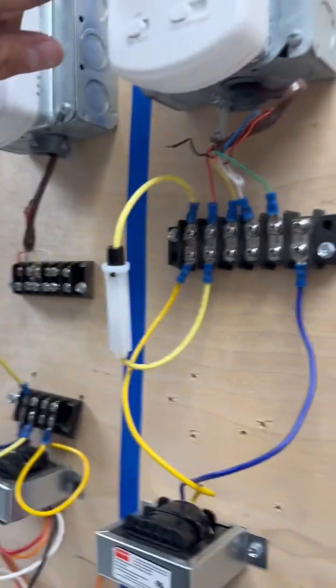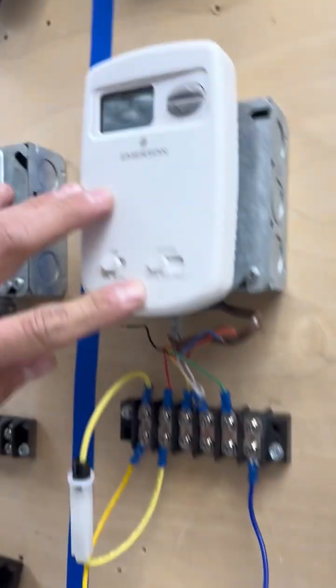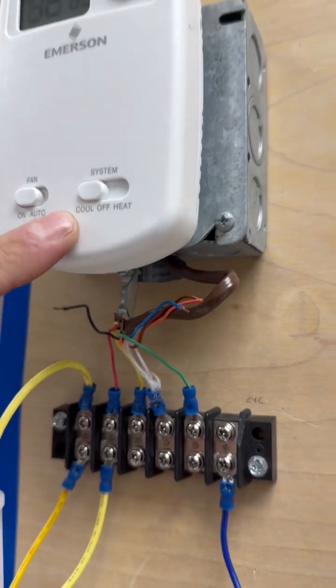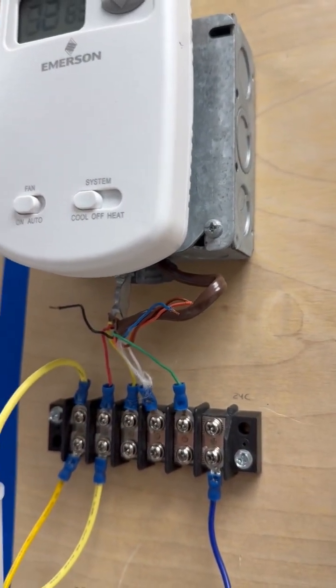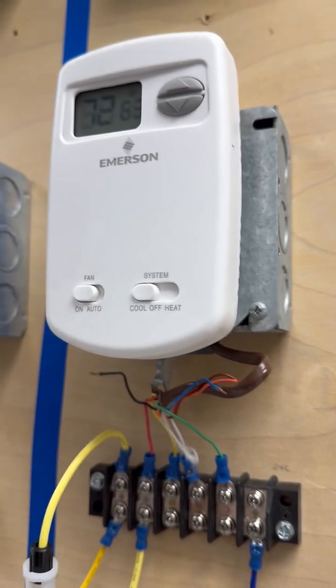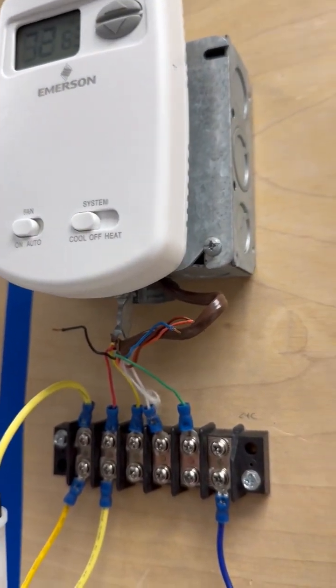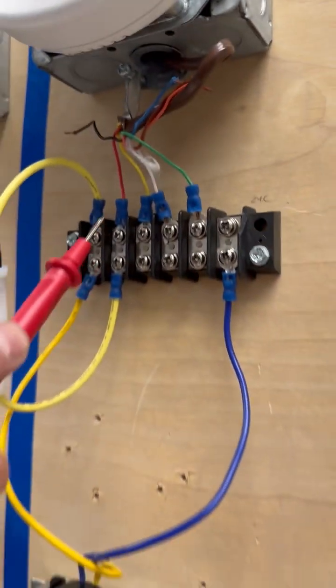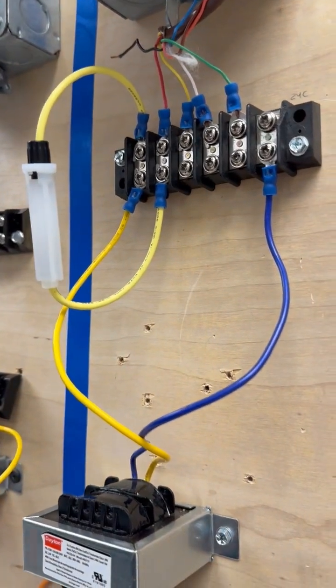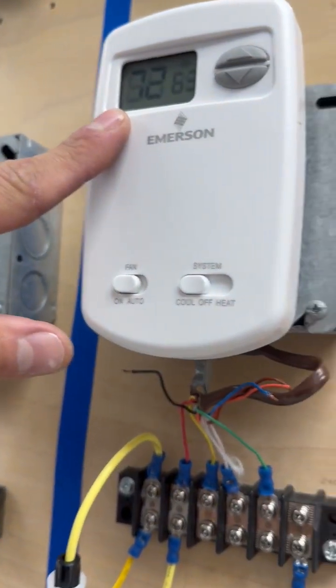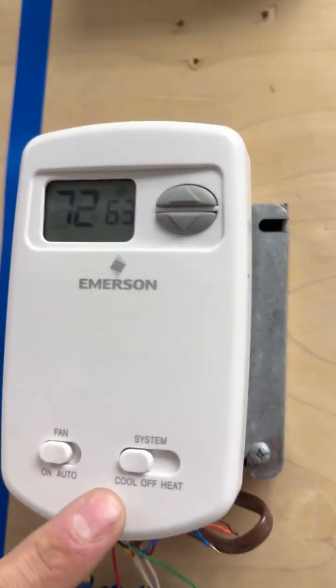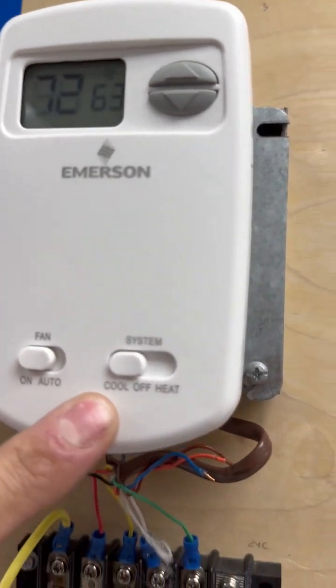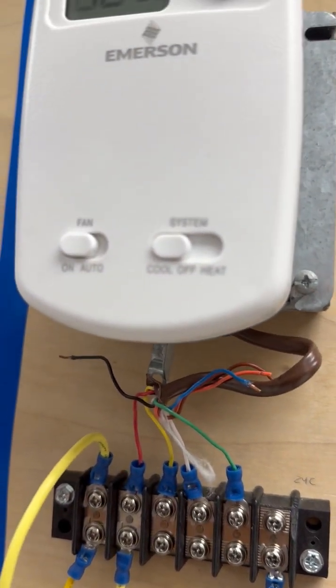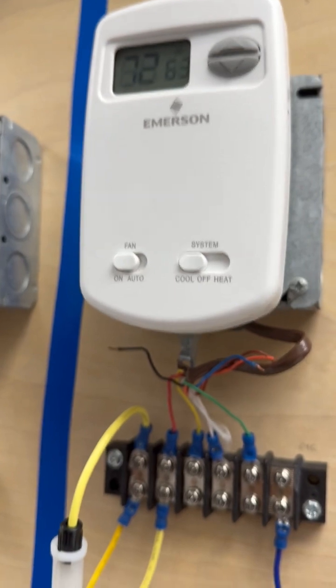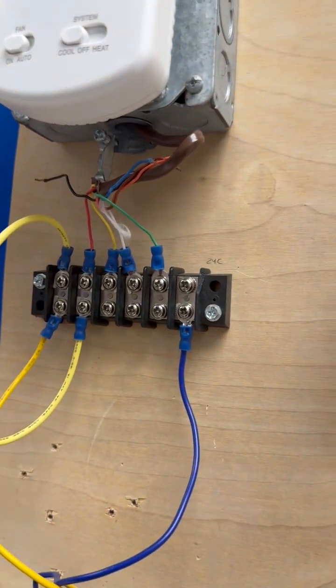Now it's important to note here, the setting is set to cool. So that means that after a certain threshold, the switch will close internally and there will be a 24 volt to 28 volt supply on one of these wires. So 72 is the ambient temperature. So that means since it's set to cool function here, the switch will close internally and there will be 24 volts feeding out through one of these wires here.